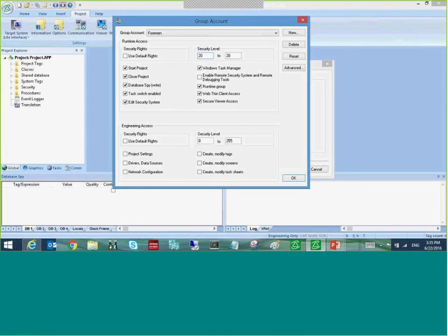And if you wanted to create any kind of group hierarchy, like operators, supervisors, plant operators, engineers, calibration, you had to create this little hierarchy of levels where an operator maybe had a range of 0 to 10, and supervisors had 0 to 20, and plant managers had 0 to 30. So basically you had this little inheritance type thing. Well, you don't have to do that anymore using InduSoft Web Studio, because if you have a user that needs to belong to more than one group, you just put that user in more than one group. Again, sort of modeling after the Windows security model.